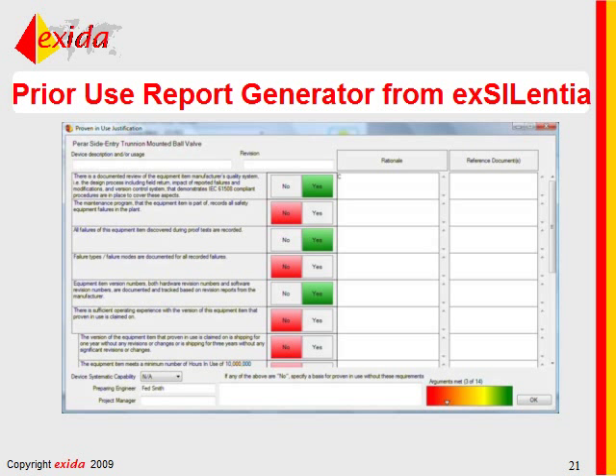See, a question popped up. Let me just see if I can find them. First one: if a SIF must include non-IEC 61508 elements, can Exida generic failure rates be used as an alternative to prior use? The simple answer is no. Exida failure rates are pieces of data that are actually valuable to you, and you can certainly use Exida or any generic failure rate data. But that alone is not enough to justify prior use. You must also have your own records of prior use justification.